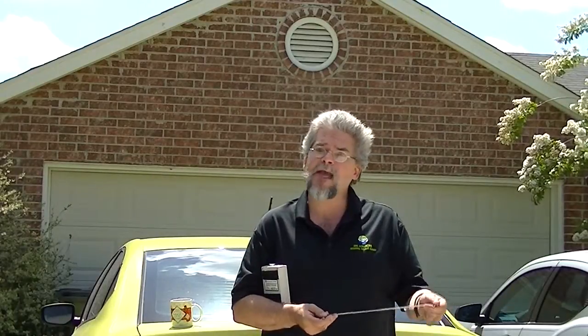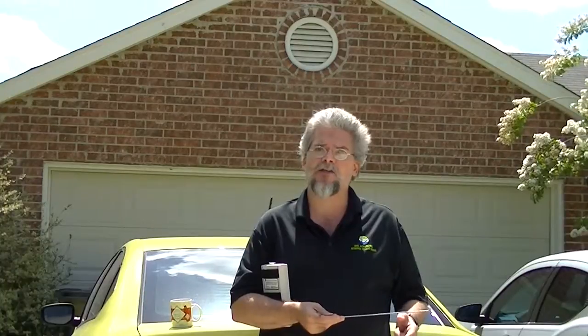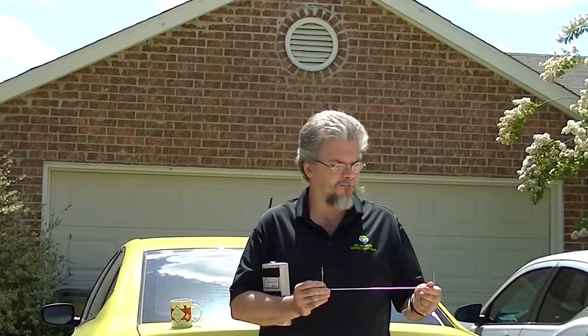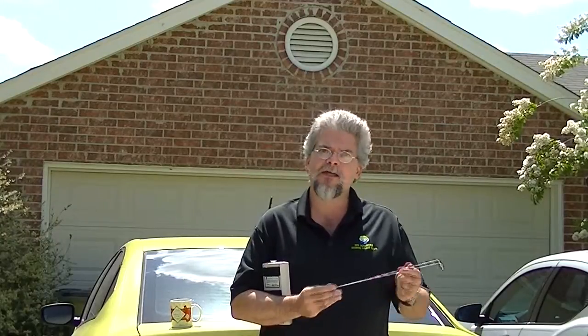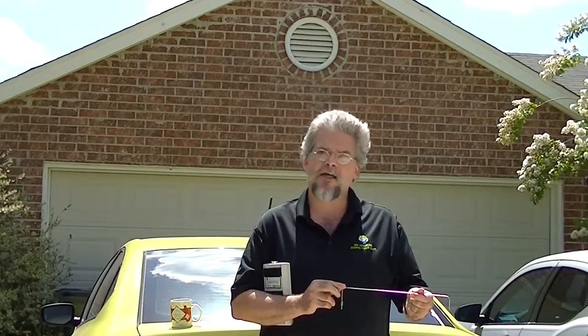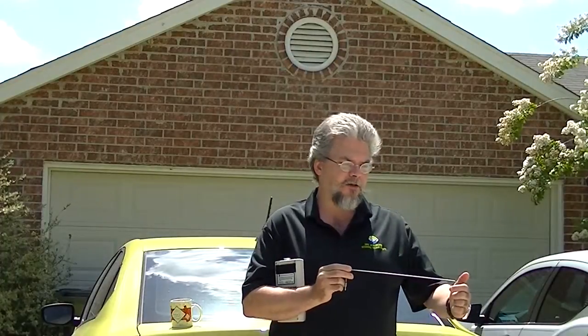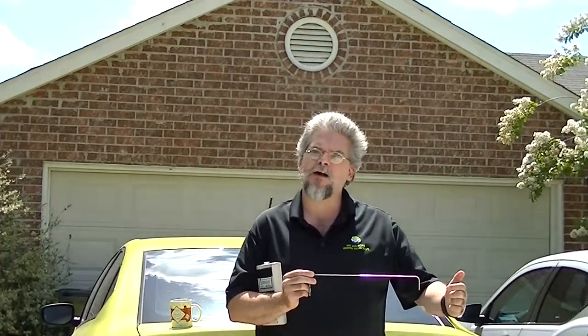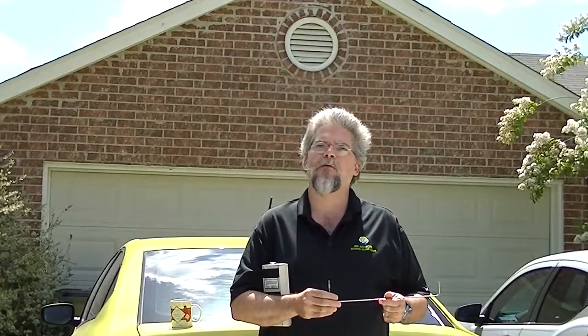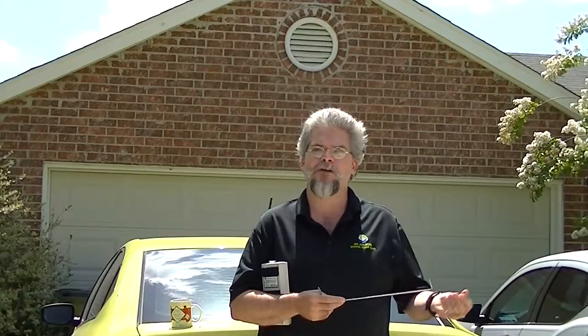We're going to go up into the attic and drill a hole into this straight metal kitchen range hood exhaust pipe. We'll insert our velocity pressure pitot tube into the duct and take a traverse reading, inserting it and taking four readings across. We'll average those readings and convert them into the kitchen range hood exhaust fan flow rate.